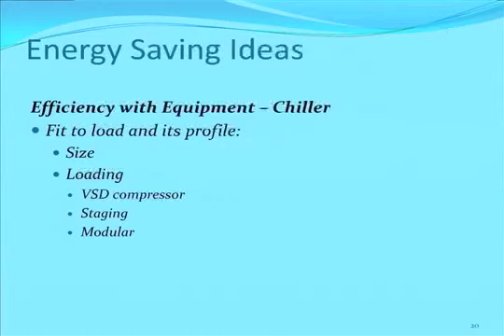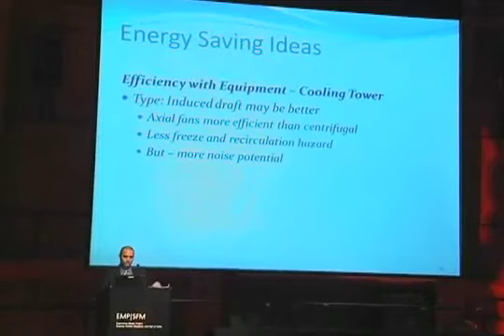Looking at the chiller itself, we want to make sure that you fit it to the load that it's trying to handle, but also to the load profile, so that it's sized appropriately, but also that it can stage on the compressor rate, or it has a variable speed compressor, or like a multi-stack, that it's modular, and that the stages can be added appropriate to the loading, so you don't have one big honking single stage chiller.